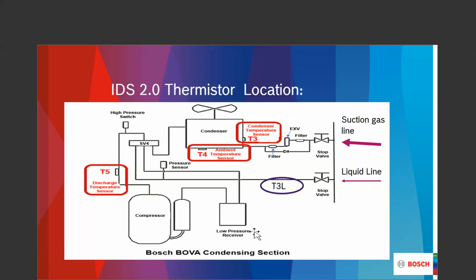So suction line gas, that's the big line. Liquid line, refrigerant line. Of course, you've got the dryer somewhere in that liquid line that comes with the unit. That liquid line, of course, is always all 3/8. So parameter check on the 2.0, number 7. That is where I'm going to get that T3L number.